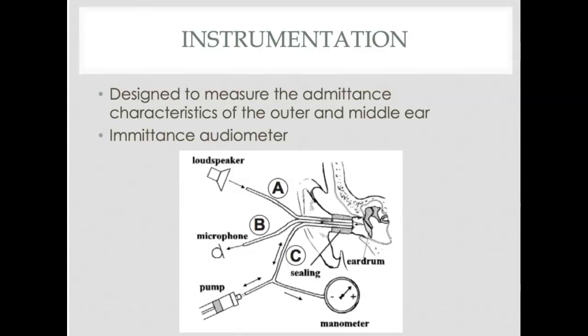Here's some of the instrumentation we use to measure acoustic admittance. Tympanometry falls underneath that umbrella, and so what we have here is a loudspeaker that plays a sound, a microphone that records the intensity of the sound, and then a pump that puts positive or negative air pressure into the ear.